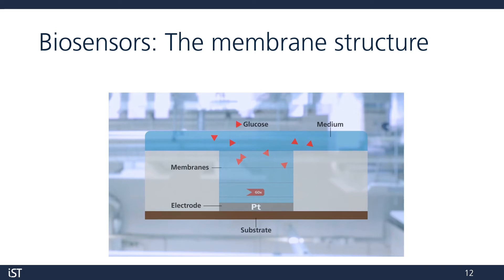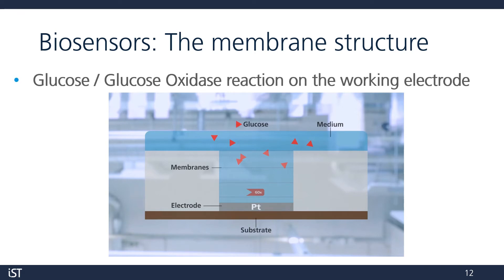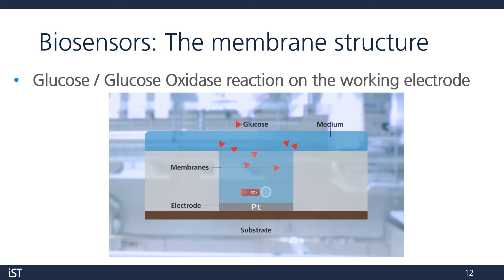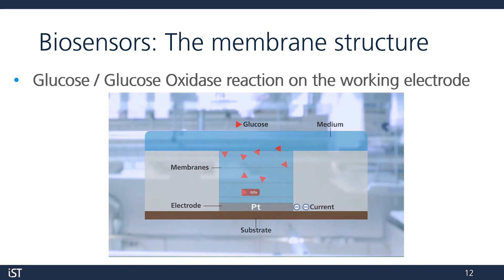Let's have a closer look at the glucose reaction over the working electrode. Here, we can see our semipermeable membrane layers. The glucose oxidase is immobilized above the platinum electrode. The glucose passes through the membrane layers and reacts with the glucose oxidase, letting off hydrogen peroxide and generating a small current when in contact with the platinum electrode.